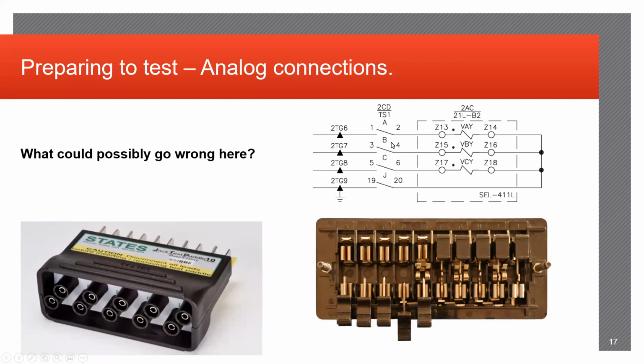When you go to plug that in, if you didn't correctly identify that the point of contact from your test set is not going directly to the relay and maybe going elsewhere, that can lead to, again, backfeeding to high voltage equipment, which can cause extreme issues. It can also go elsewhere to other pieces of equipment, again, in-service relays that may be connected in parallel, cause misoperations, just more and more damage and more issues. So as long as you can confidently identify that where you plug in your current and voltage injections is directly correlated only to the relay that you're going to be testing, then you should be all set.